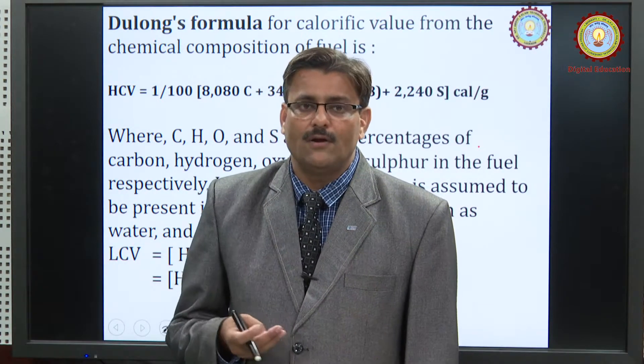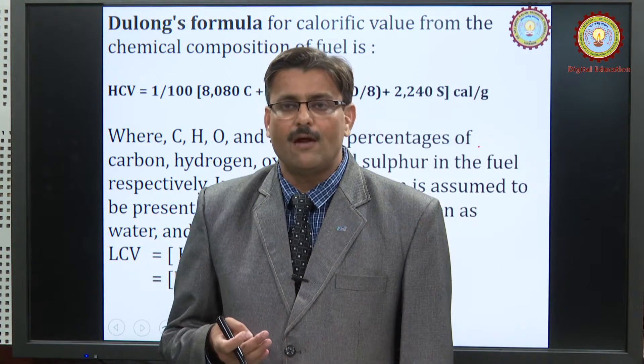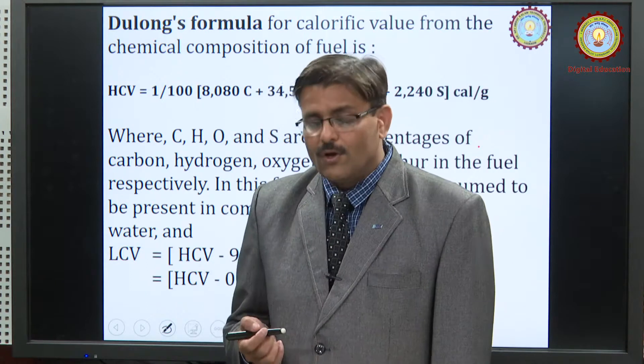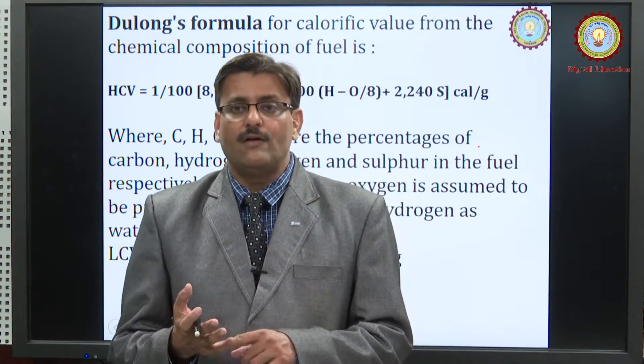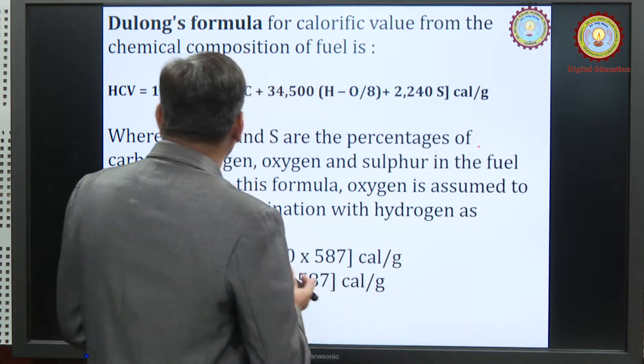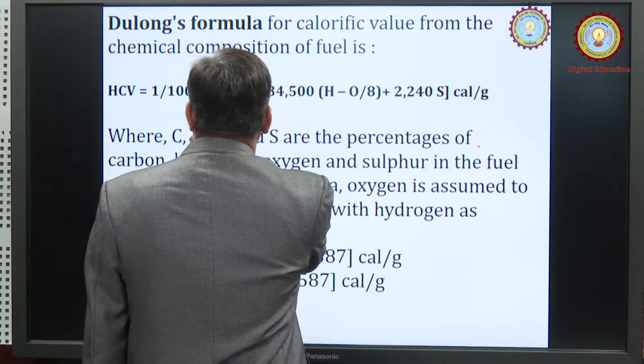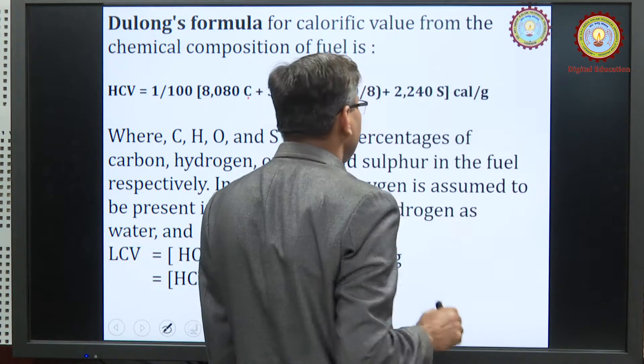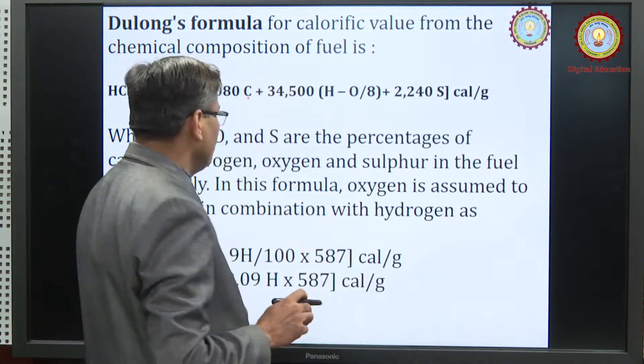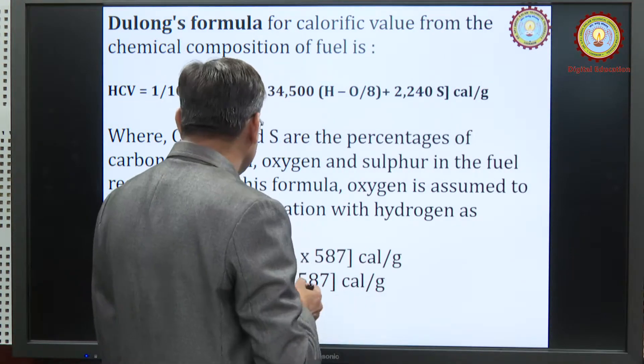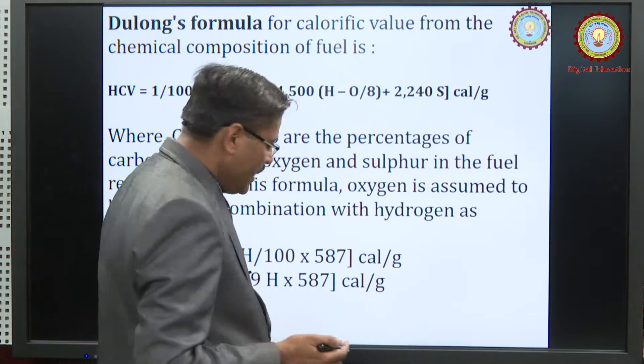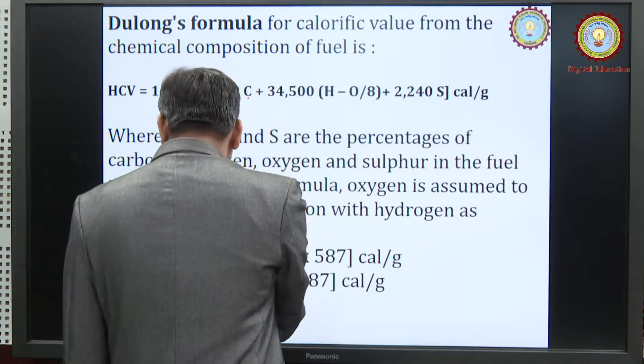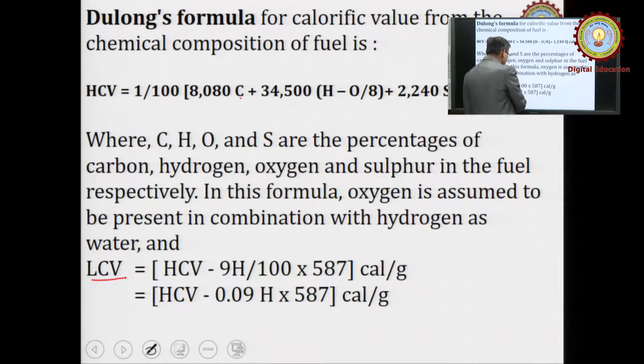By estimation of carbon, hydrogen, oxygen, and sulfur: if you know the percentage of these elements in a fuel, you can directly use Du Long's formula to calculate gross calorific value. The formula is: HCV = (1/100) × [8080C + 34500(H − O/8) + 2240S] calories per gram, where C, H, O, and S are the percentages of the respective elements. After calculating higher calorific value, LCV can be calculated by subtracting (9H/100) × 587 from the GCV.